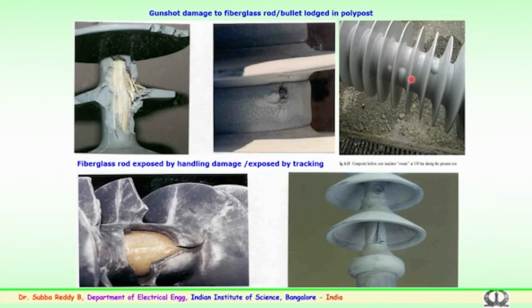Here you can see that during the manufacturing stages, water bubbles or air bubbles can form. In case the insulators are being used in the field over a period of time, because of the electrical stress these bubbles could break and water could seep in, and the failure is likely to happen. So, these again are some of the earlier failures of polymer insulators which have been seen by the utilities.